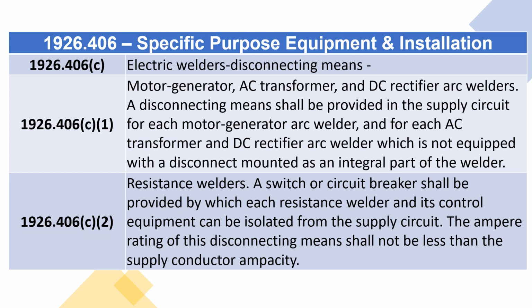1926.406(c) Electric welders, disconnecting means. 1926.406(c)(1) Motor generator, AC transformer, and DC rectifier arc welders. A disconnecting means shall be provided in the supply circuit for each motor generator arc welder, and for each AC transformer and DC rectifier arc welder which is not equipped with a disconnect mounted as an integral part of the welder. 1926.406(c)(2) Resistance welders. A switch or circuit breaker shall be provided by which each resistance welder and its control equipment can be isolated from the supply circuit. The ampere rating of this disconnecting means shall not be less than the supply conductor ampacity.